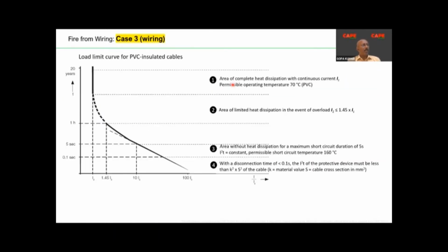With respect to wires, the wire must have a life and must withstand a certain temperature. 70 degrees centigrade is the maximum allowed temperature, and it is supposed to work for 20 years of life. If the current is more than about 1.45 times the rated current carrying capacity of the wire, then the protective device is supposed to trip. While selecting the wire, you are supposed to go through this particular chart and select it appropriately so that the wires are not overloaded. Very important.